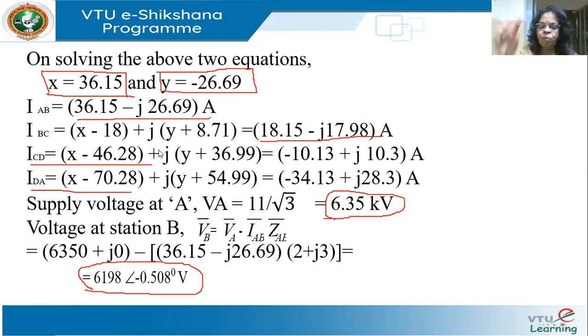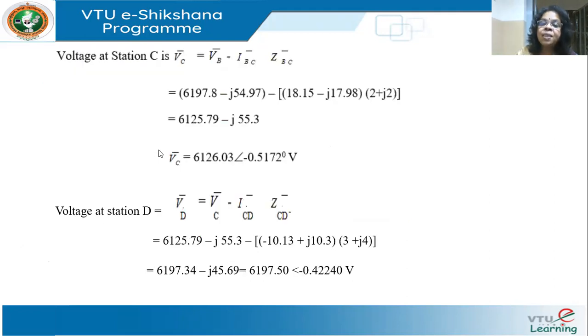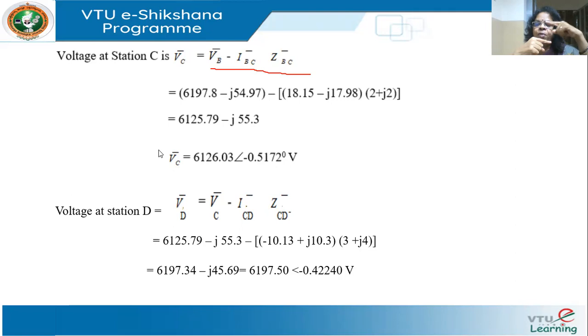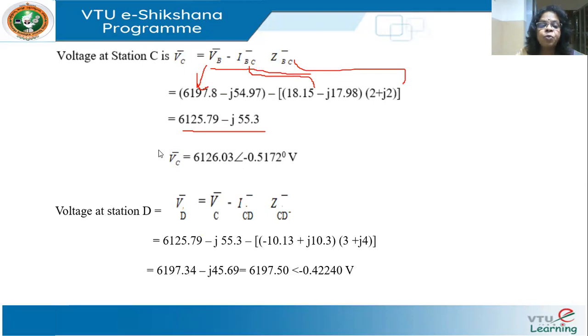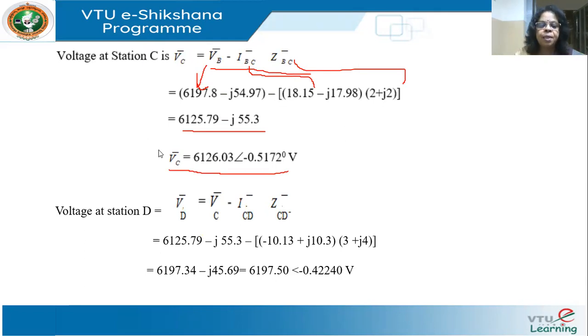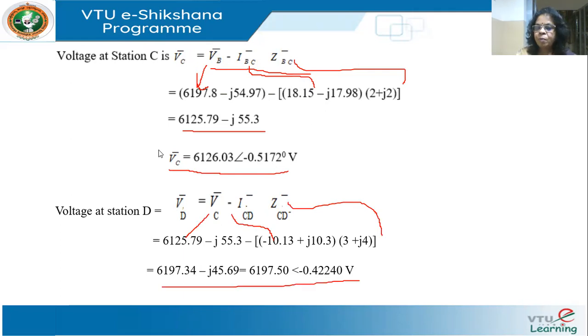The voltage at B is less than the supply — obviously, because we've traveled along the line. Moving from B to C: VC = VB − IBC × ZBC, giving 6125.79−j55.3, which is further reduced. Then from C to D: VD = VC − ICD × ZCD. The voltage keeps decreasing as we move from one node to the next.